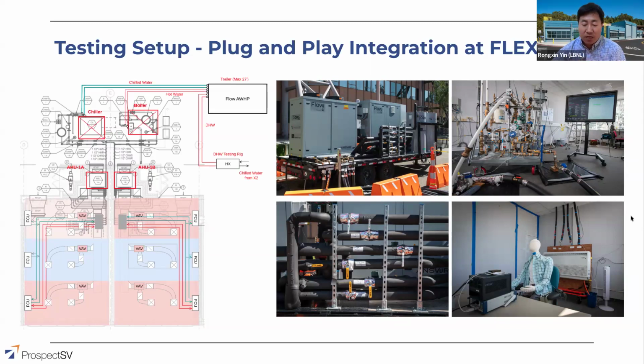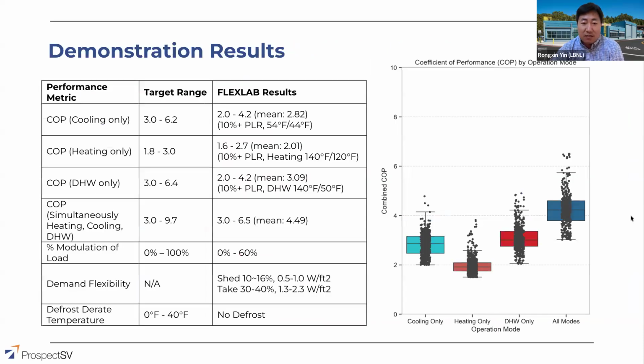For phase one, we have the winter testing, and we configure the test bed to be an air handling unit plus the VAV terminals for each zone. And the reason why we put the fan coil unit here is that the existing reheat uses electric resistance. To make use of the hot water from the unit, we disable the existing electric reheat and use the fan coil unit for the reheat. And for some testing, we just configure a DOAS plus the fan coil unit. And let's move on to the next slide.